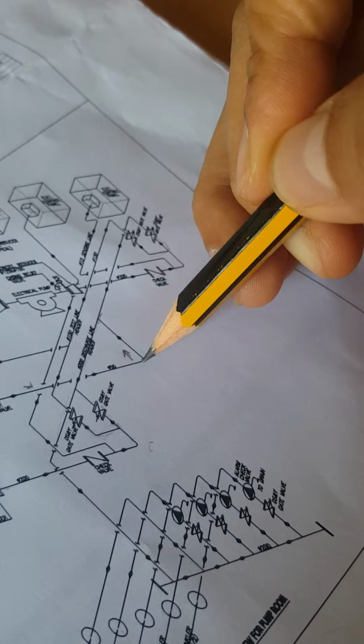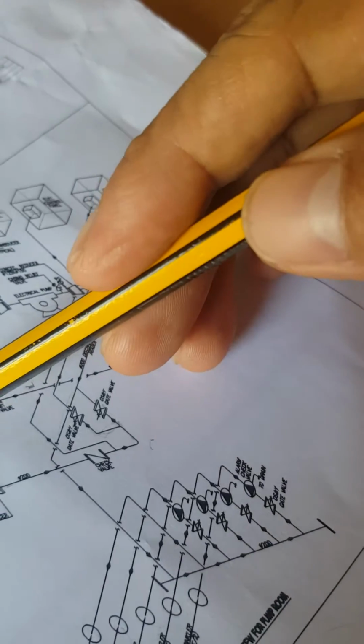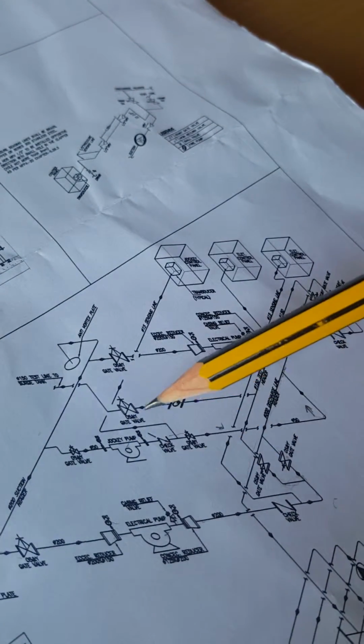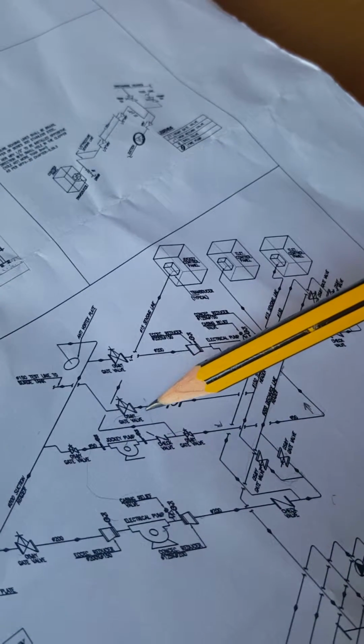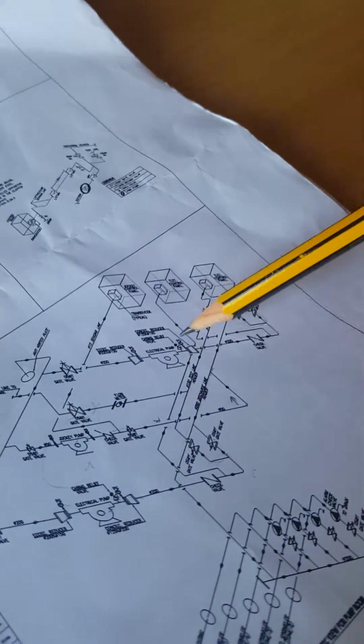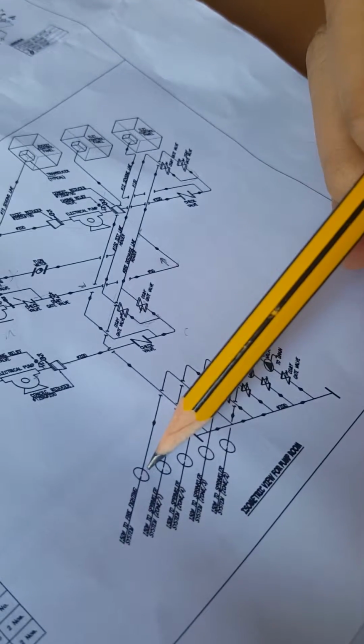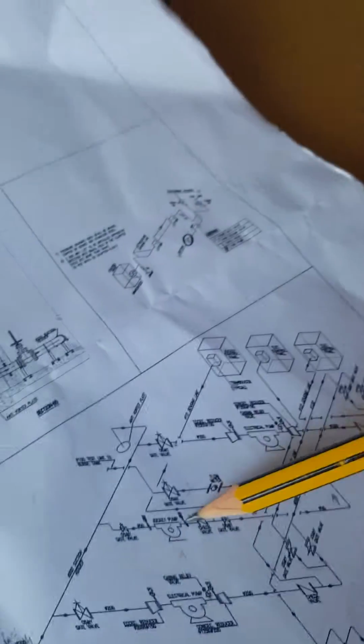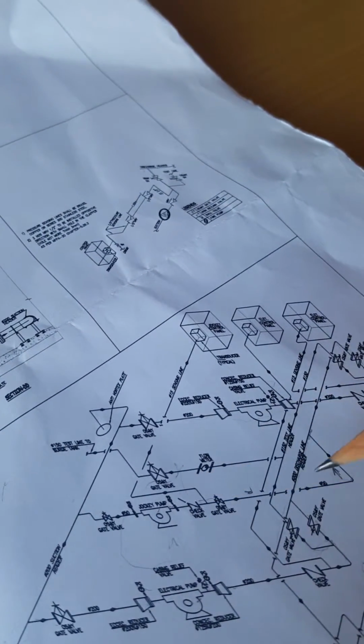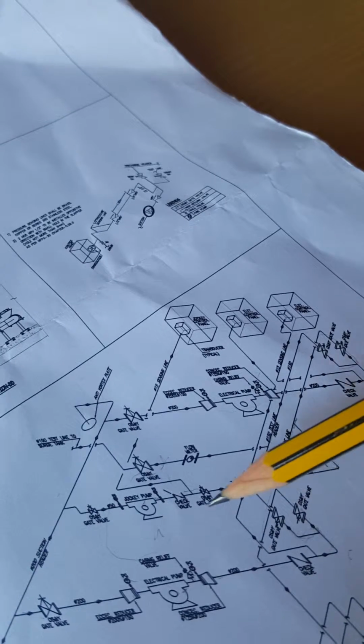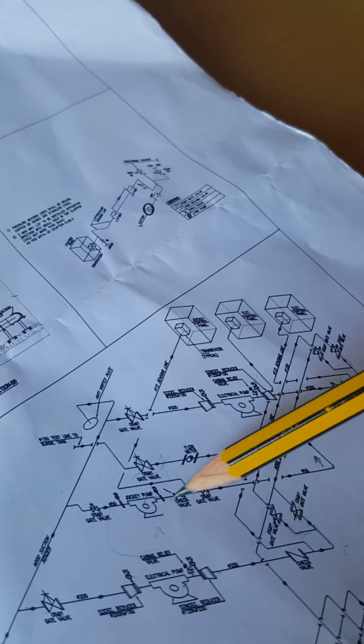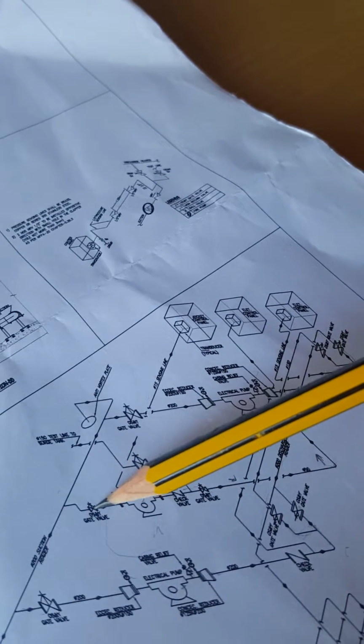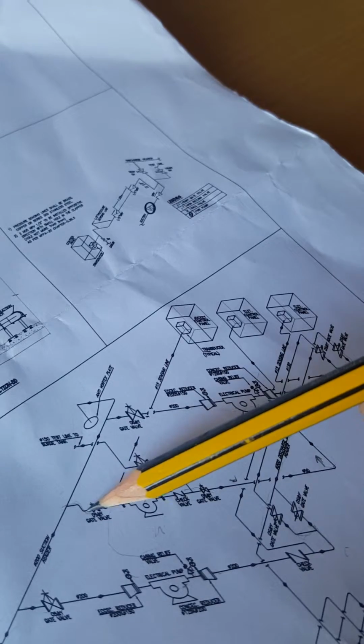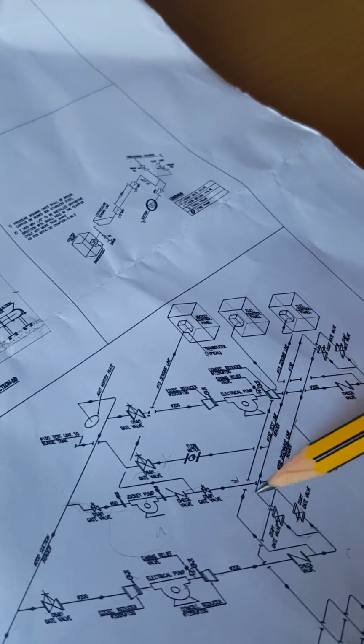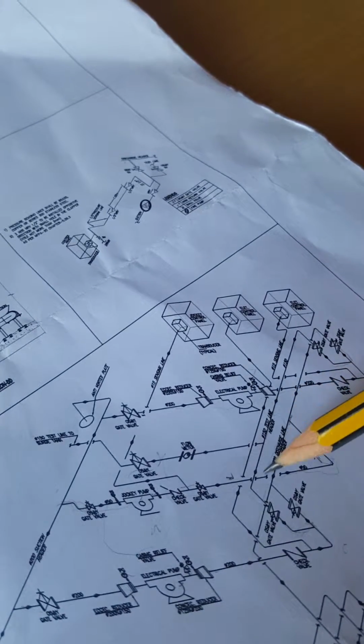of the jockey pump, because this jockey pump will enforce or assist the main electrical pump during the opening of these fire sprinklers. So this jockey pump is connected also to the discharge line with its own gate valve and check valve, and the gate valve on the other side connects to the suction header. So it will suck the water over here also, going to the discharge line.